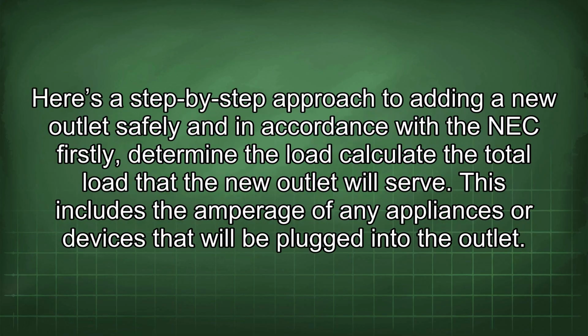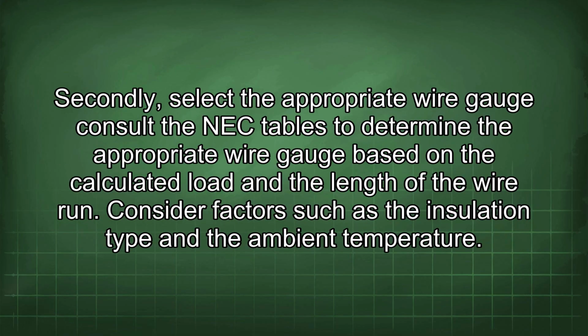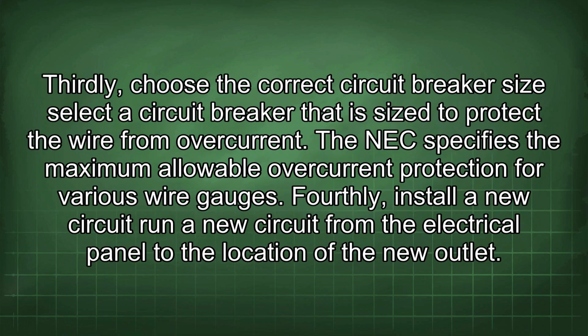Here's a step-by-step approach to adding a new outlet safely and in accordance with the NEC. Firstly, determine the load. Calculate the total load that the new outlet will serve. This includes the amperage of any appliances or devices that will be plugged into the outlet. Secondly, select the appropriate wire gauge. Consult the NEC tables to determine the appropriate wire gauge based on the calculated load and the length of the wire run. Consider factors such as the insulation type and the ambient temperature. Thirdly, choose the correct circuit breaker size. Select a circuit breaker that is sized to protect the wire from overcurrent. The NEC specifies the maximum allowable overcurrent protection for various wire gauges.